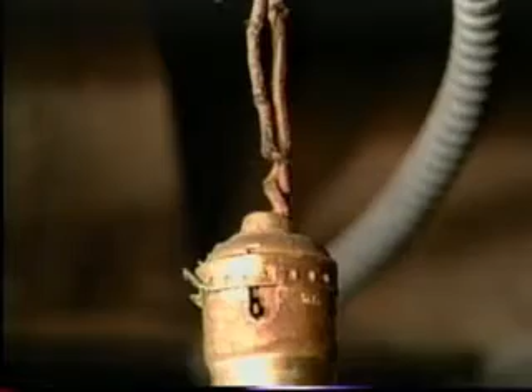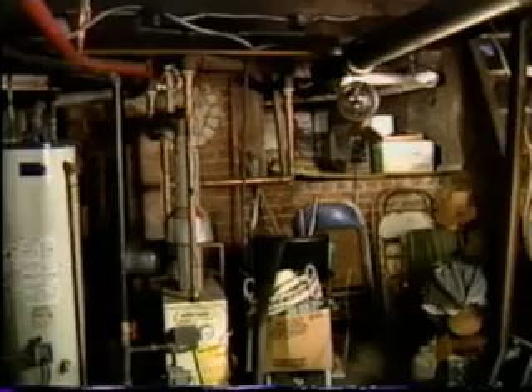Here is some wiring where the connections have corroded, the insulation has cracked and separated from the wires, and there are scorch marks indicating overheating. Here is an older kind of wiring which is only rated for use out in the open. When covered with insulation, it can overheat and create a real fire hazard. If you add insulation to your house, be careful not to cover wiring and fixtures unless an electrician has certified that they are rated for such conditions.